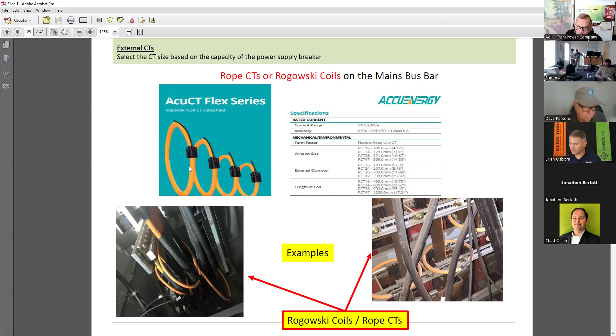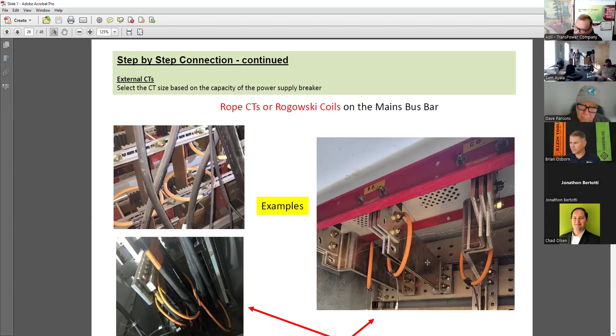Here are some examples to show what I meant. You see the width of this is a 5000 amp bus bar. These are 2000 amp or 1500 amp services coming from the utilities. Examples of the CTs on the main bus bar. You want to find a very clear spot because these CTs need to go in at a particular spot, and you'll see that as we go through the slides.